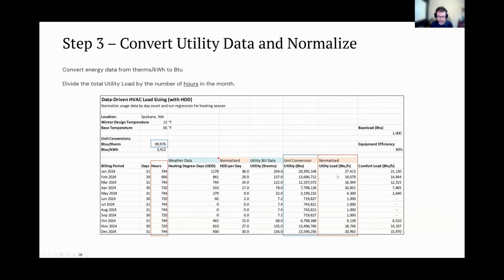And then you've got to normalize it. Same thing, except I like to normalize this by the hours, so our units end up in BTUs per hour, which again is industry standard. That's how equipment is sized in the United States, so it's easy to use these numbers. This will already feel familiar if you're used to working with heating and cooling loads.